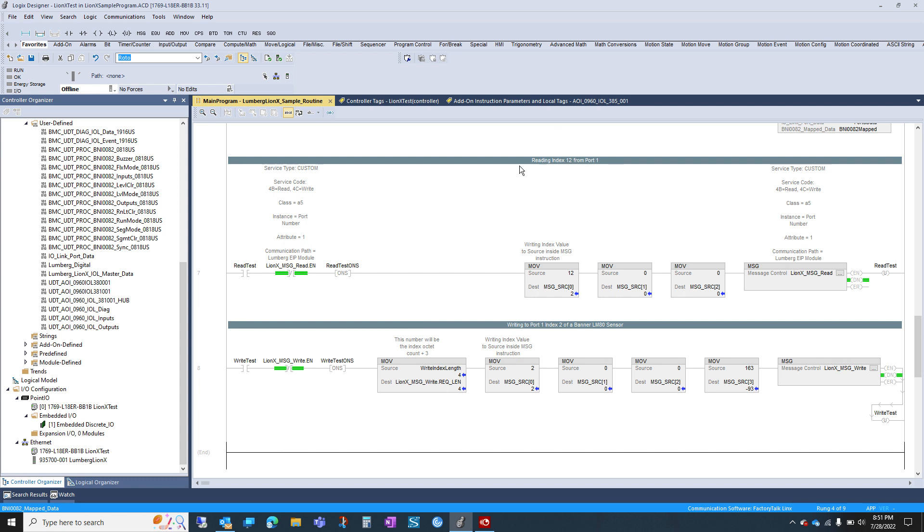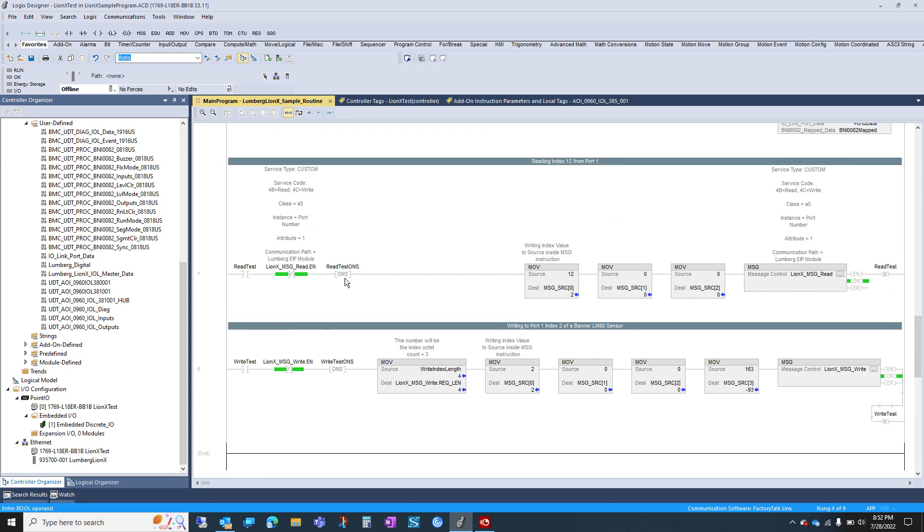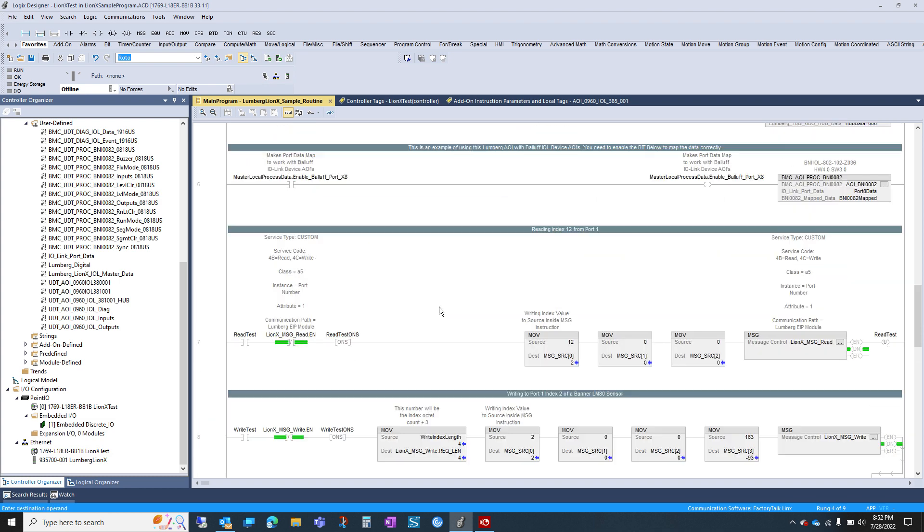And then we also are reading indexes. So this is reading the parameters of your device. Not necessary. You don't need to do this. This is just some people have asked for it. You can read and write parameters of your IO-Link device. In this case, we're reading port 1 and index 12 of what this device was. And that's what this read is. So again, not necessary. You can delete these rungs if you don't need to do any reading and writing from the PLC. You can read parameters and write parameters from the block themselves as well as upload the IODD file. And that's it.